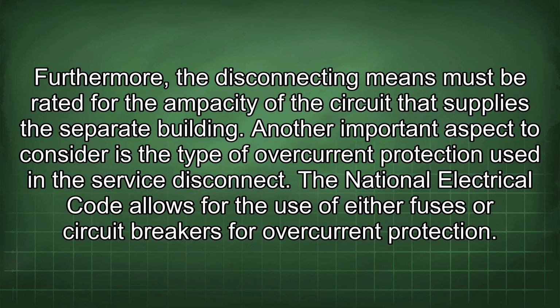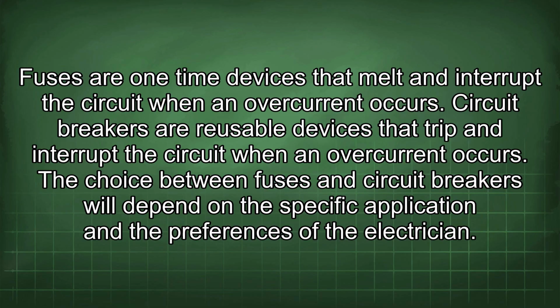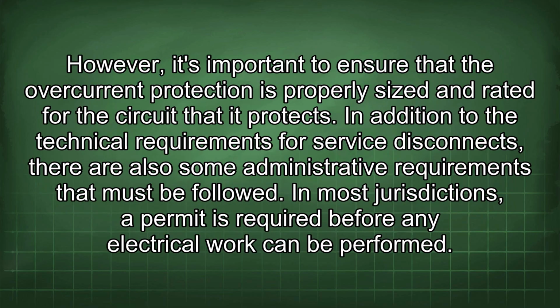Another important aspect to consider is the type of overcurrent protection used in the service disconnect. The National Electrical Code allows for the use of either fuses or circuit breakers for overcurrent protection. Fuses are one-time devices that melt and interrupt the circuit when an overcurrent occurs. Circuit breakers are reusable devices that trip and interrupt the circuit when an overcurrent occurs. The choice between fuses and circuit breakers will depend on the specific application and the preferences of the electrician. However, it's important to ensure that the overcurrent protection is properly sized and rated for the circuit that it protects.